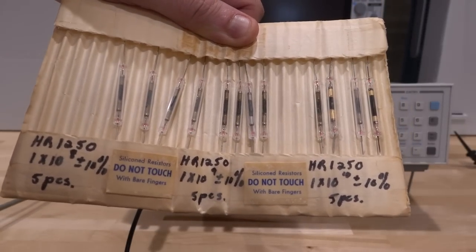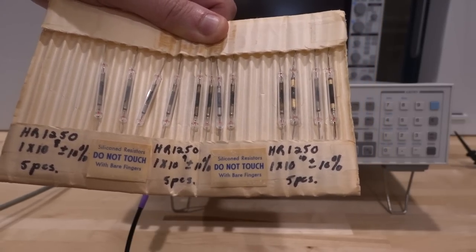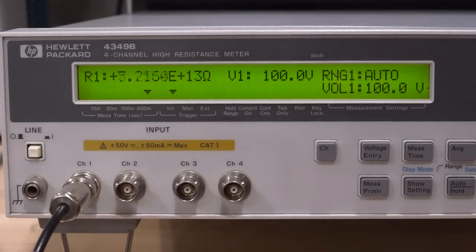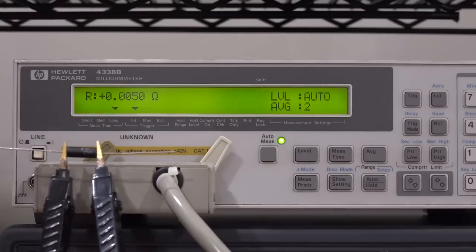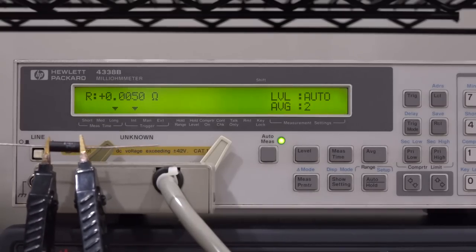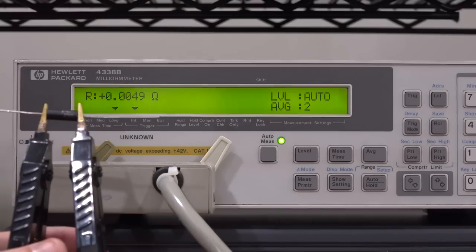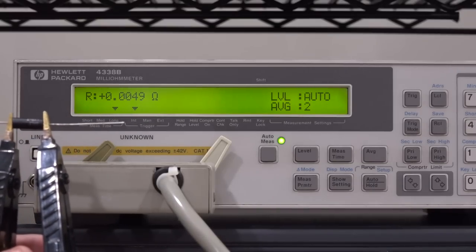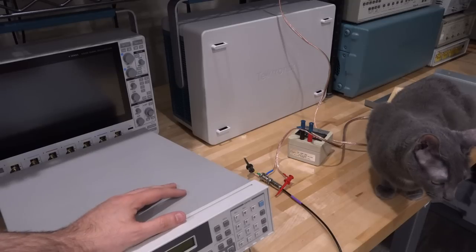I also have some resistors rated at 1 × 10¹⁰ Ω — ten times larger. At 100 volts, one reads 1.17 × 10¹⁰ and another reads 8.2 × 10⁹, showing these old resistors are quite far off their nominal values. For fun, at the exact opposite range, the 4338B measuring a 5 milliohm resistor measures it very precisely once the setup stabilizes. These are the two extreme ends of the instrument range. I hope you enjoyed the video — even though the repair itself wasn't very interesting, hopefully the experiments were. See you next time.